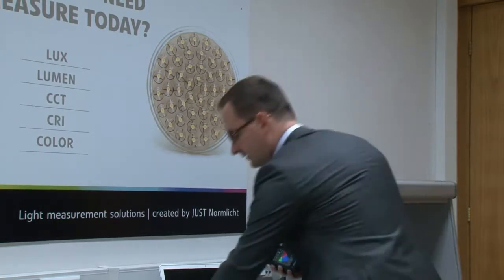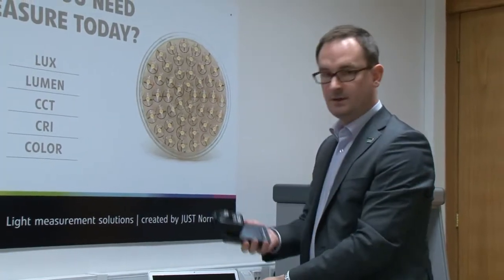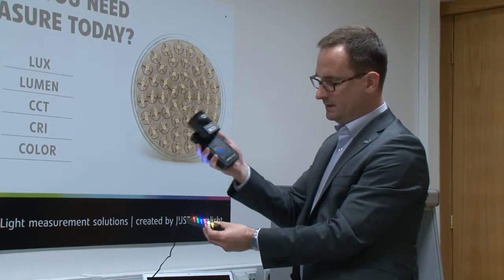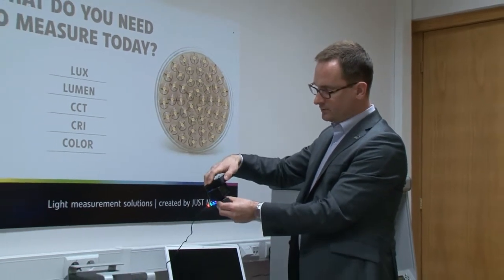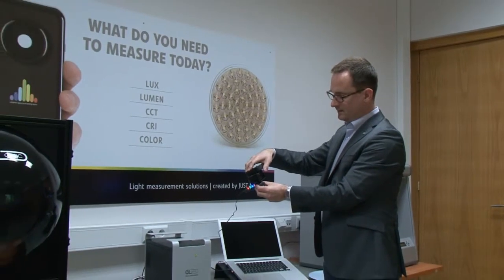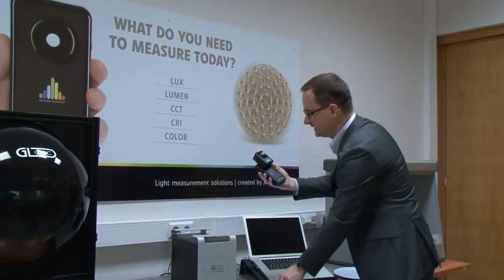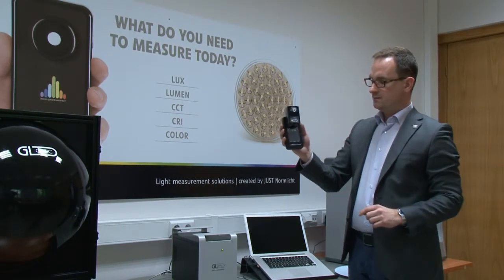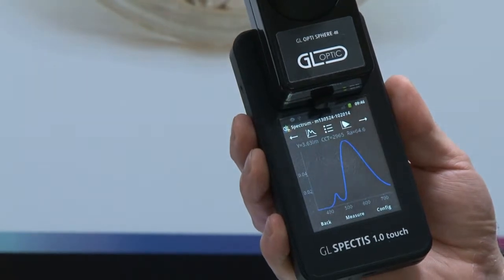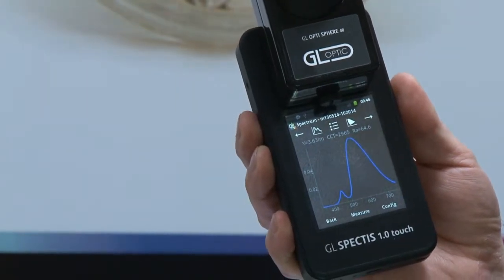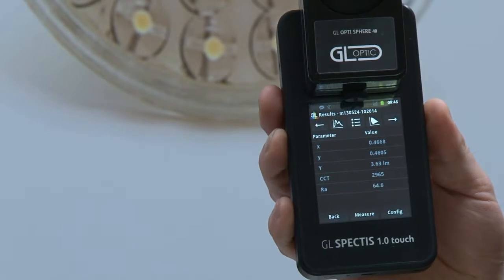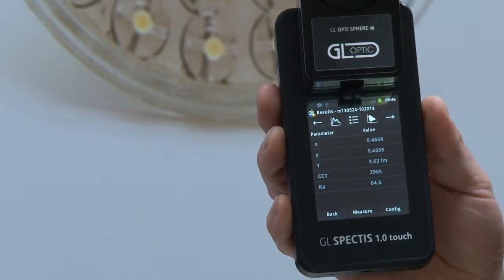This is just an example of LEDs which we can measure. I am covering one of these LEDs with our integrating sphere, pushing the measurement button, and then I get the results directly on the screen. I have the spectral power distribution, and the selected values which are: XY color coordinates, lumen output, color temperature, and CRI index.